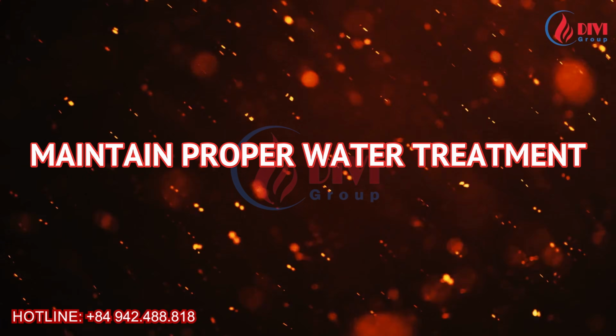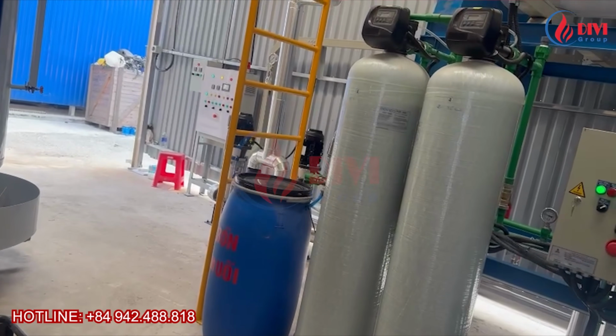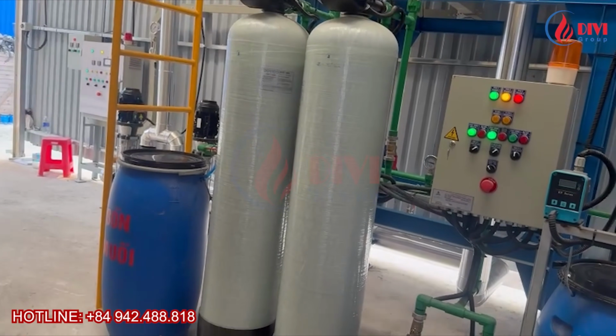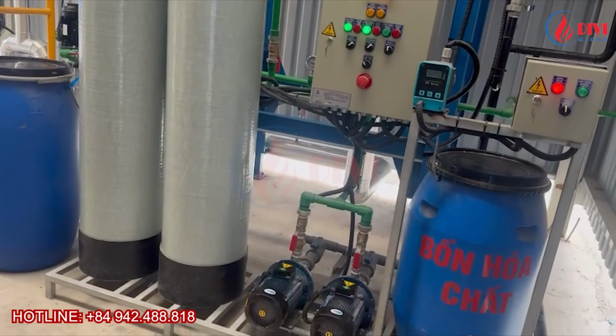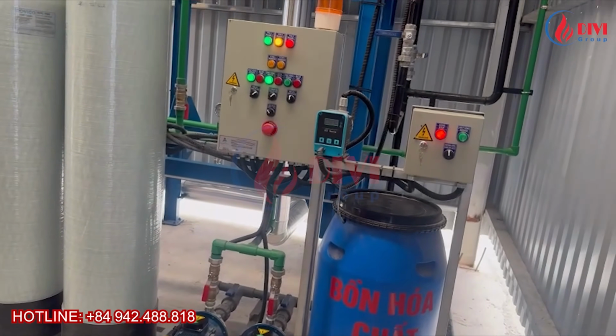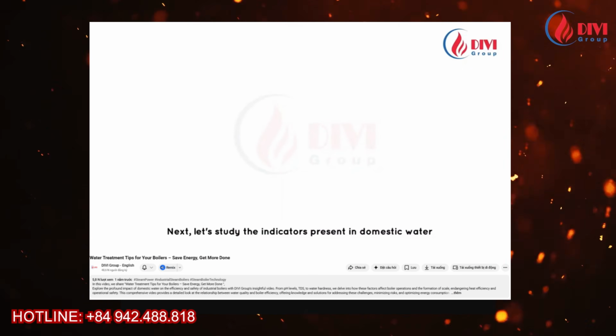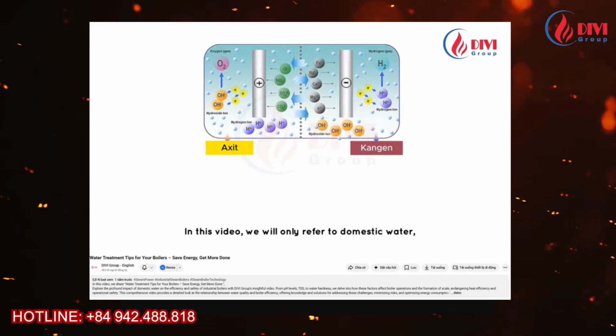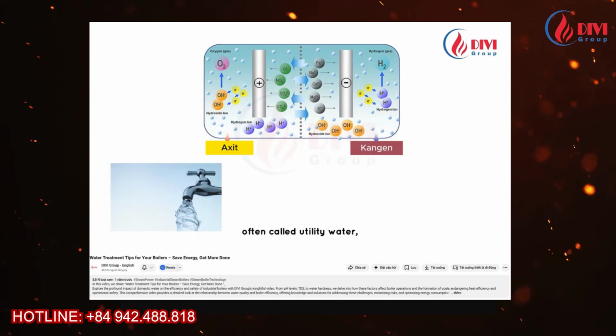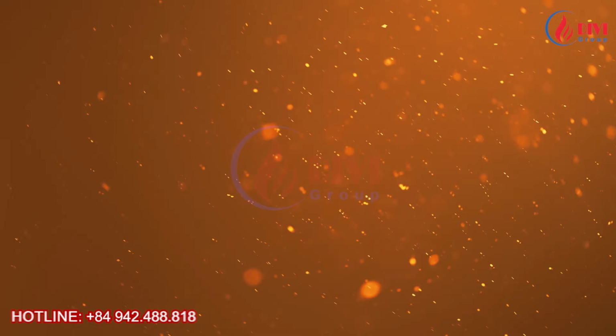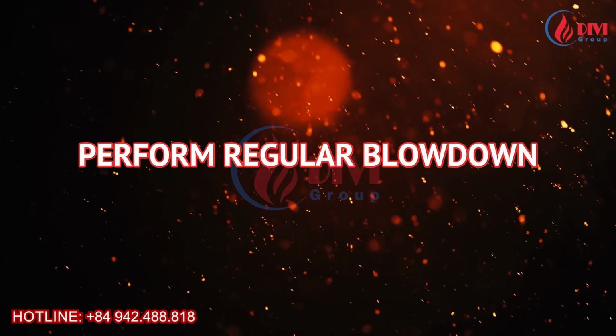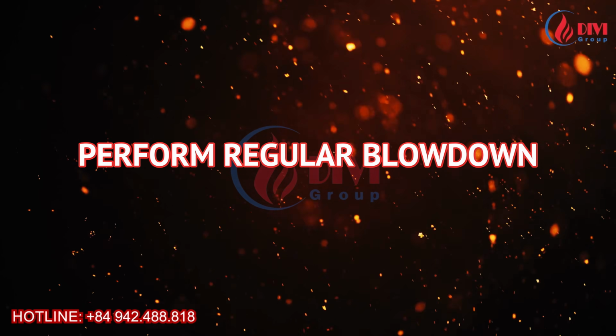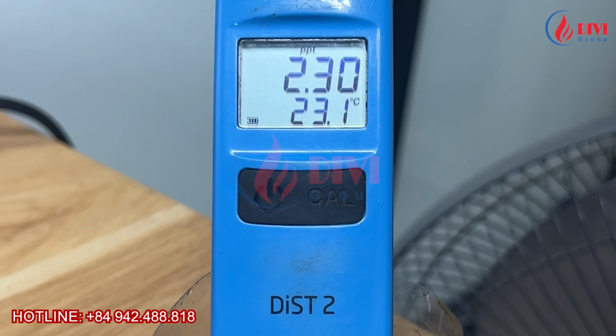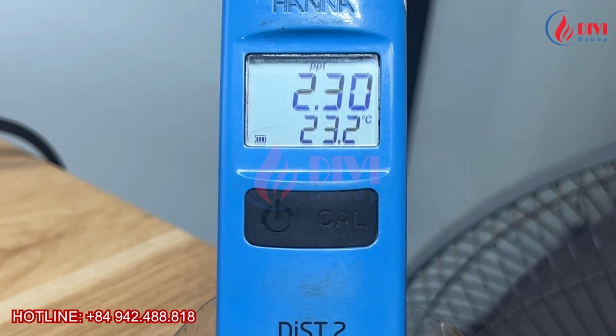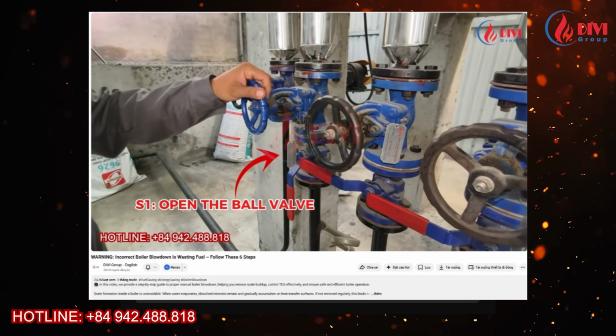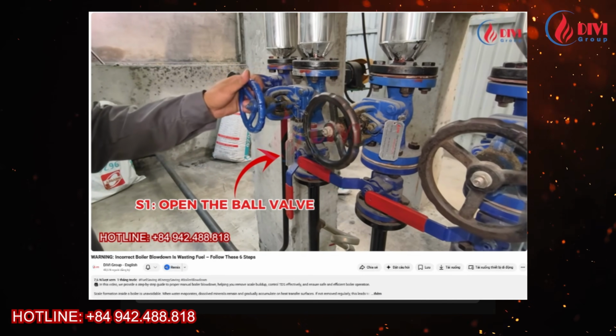Second, maintain proper water treatment. Use water treatment chemicals correctly to minimize scale formation and control feed water hardness within recommended limits. For more details, you can watch our video, Why Water Treatment Chemicals Are Essential for Boilers, on the DIVI channel. Third, perform regular blowdown to keep TDS levels within the recommended range. Boiler blowdown should be based on actual TDS readings. For more information, please refer to our video, Boiler Blowdown Guidelines, on the DIVI channel.